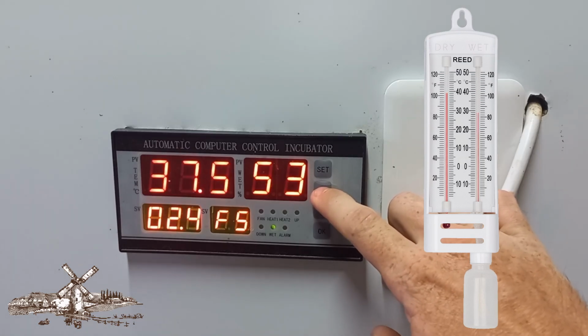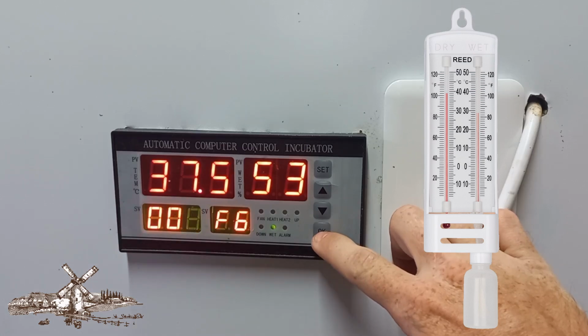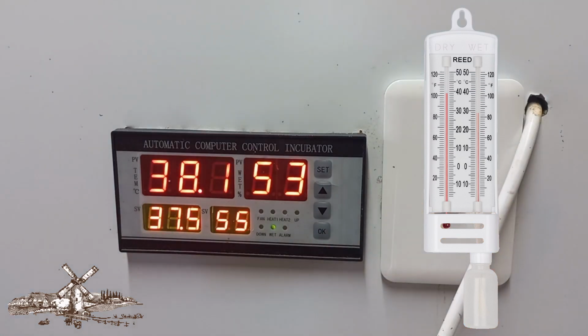And what we expect to see, if you did this correctly, is the temperature of the controller rapidly increasing up to 40 degrees Celsius. Now, it's important to notice that my temperature in my machine right now is actually not going up. My temperature is actually staying the same. The reason why we see this is because the controller has only just figured out that in fact the temperature is 40. And so it displays a new temperature of 40, which matches my dry bulb thermometer. And you'll see that your alarm light comes on, your extraction fan light turns on. Hopefully you have an overtemp inside your machine.